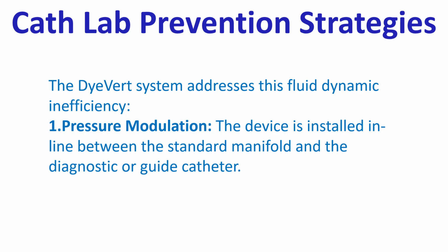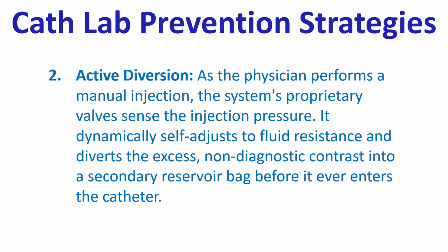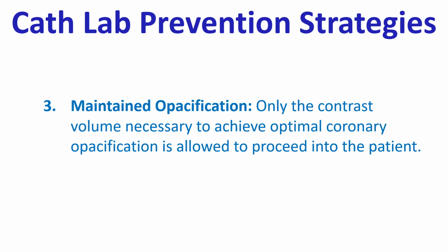Pressure modulation. The device is installed in line between the standard manifold and the diagnostic or guide catheter. Active diversion. As the physician performs a manual injection, the system's proprietary valve senses the injection pressure. It dynamically self-adjusts to fluid resistance and diverts the excess non-diagnostic contrast into a secondary reservoir bag before it ever enters the catheter. Maintained opacification. Only the contrast volume necessary to achieve optimal coronary opacification is allowed to proceed into the patient.